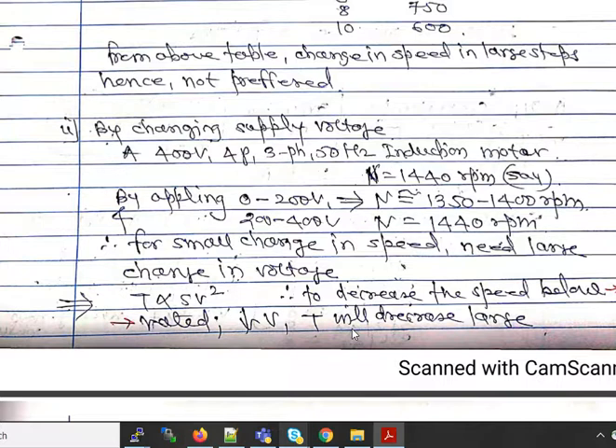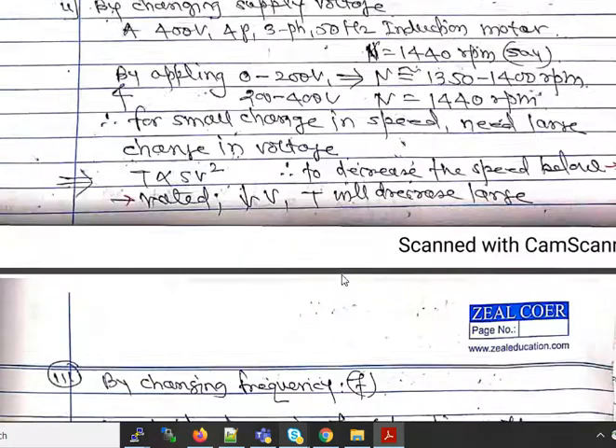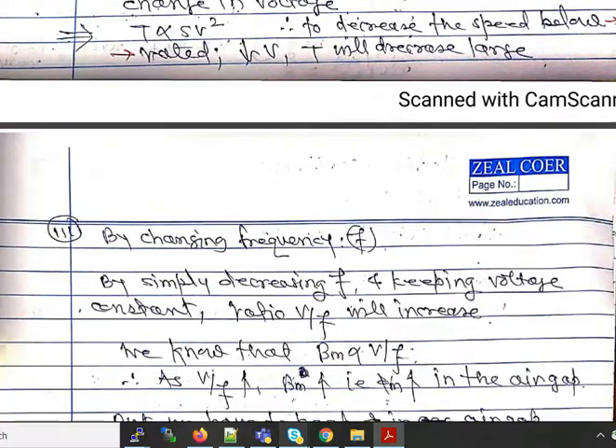The second issue is that torque is directly proportional to the square of supply voltage. Therefore to decrease the speed below rated value we must decrease the voltage. When the voltage is at 50 percent, we get only 25 percent of the torque. This large decrease in torque as voltage decreases makes this method also not suitable.